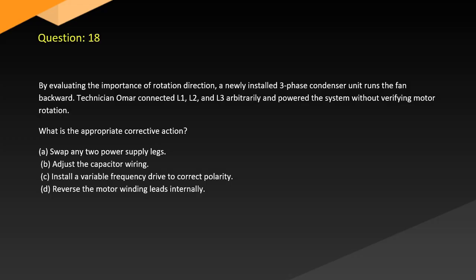Question 18. By evaluating the importance of rotation direction, a newly installed three-phase condenser unit runs the fan backward. Technician Omar connected L1, L2, and L3 arbitrarily and powered the system without verifying motor rotation. What is the appropriate corrective action? A. Swap any two power supply legs. B. Adjust the capacitor wiring. C. Install a variable frequency drive to correct polarity. D. Reverse the motor winding leads internally.